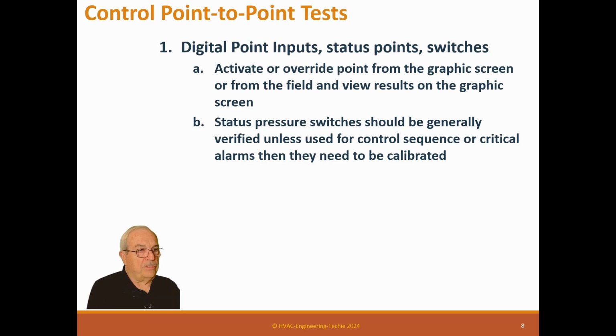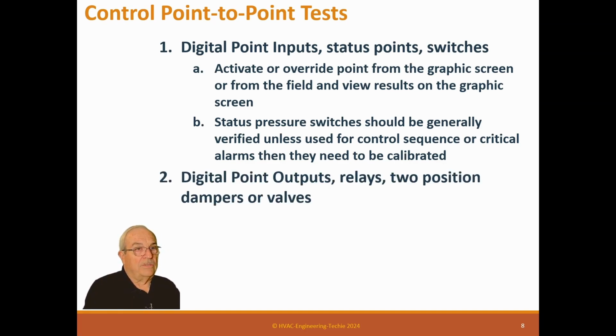One, on the computer screen, you can turn it on, turn it off. You can override its status on the screen to see what happens. Or you can actually do it in the field. You can go up to a disconnect switch and turn the pump off, and it should notify the screen that it's off now. And we do that in failure testing. So if you want to see if the pump rotates, you turn it off on the field at the disconnect. That's a failure, and you do it that way.